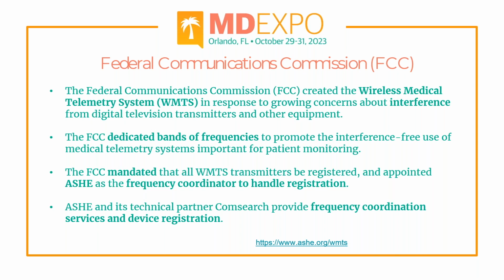And what the FCC did was dedicate bands of frequencies to promote interference-free use of medical telemetry systems that were important for patient monitoring. And it's a mandate from the FCC that all WMTS transmitters must be registered, and they appointed ASHE, the American Society of Healthcare Engineering, as the frequency coordinator for handling the registration.